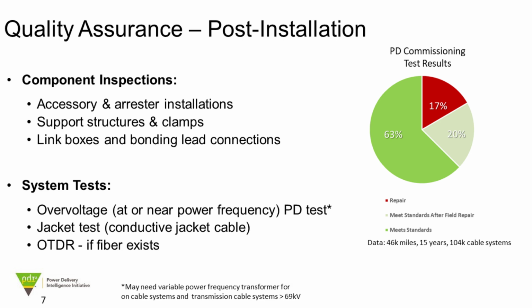Then the actual test itself, we're advocating that we really look to the industry experience of testing 100% of reels and pre-built terminations and joints in the factory with an overvoltage at or near power frequency PD test. And there are standards for this in the factory, and if we can mimic these types of tests in the field, that's going to give us the confidence that the system is installed properly from a dielectric standpoint.